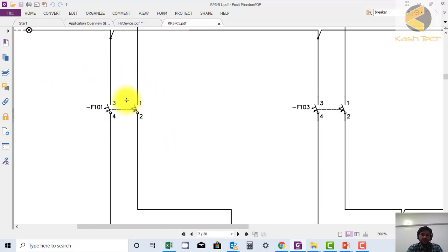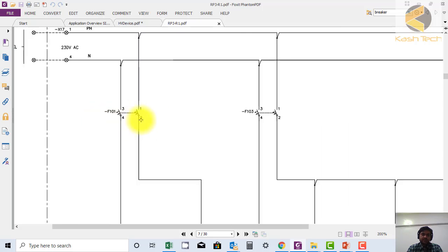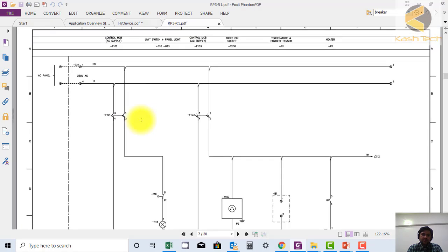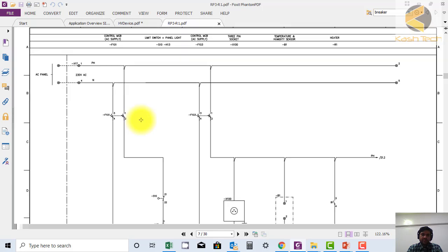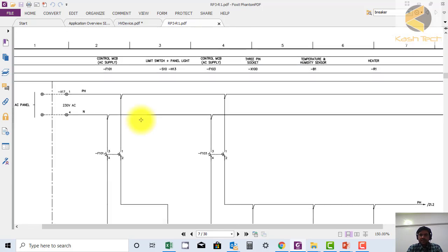Now let's look at the symbol of the MCB. F101 — as already explained, odd contacts are normally used for incoming supply connections, and even contacts are used to connect the outgoing supply. If in a drawing you find the reverse, you can raise a comment. This is basically the standard default convention.